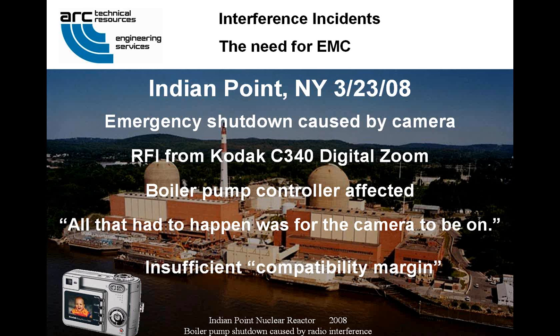More stringent specifications of the control equipment was clearly called for, since normal operation of this plant was susceptible to upset by nearby consumer electronics. This indicates an insufficient compatibility margin between the emissions levels from the cameras or other interference sources nearby and the susceptibility thresholds of the controls and their wiring in the cabinets.